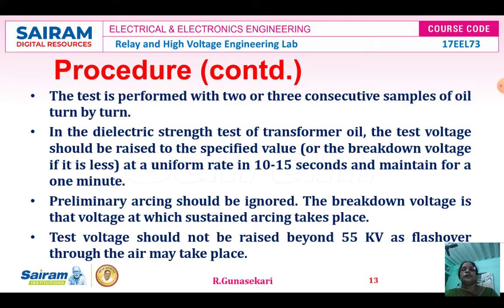The test is performed with 2 or 3 consecutive samples of transformer oil, turn by turn. The readings are also taken 2 or 3 times. The average value only is considered as the breakdown strength of the transformer oil.